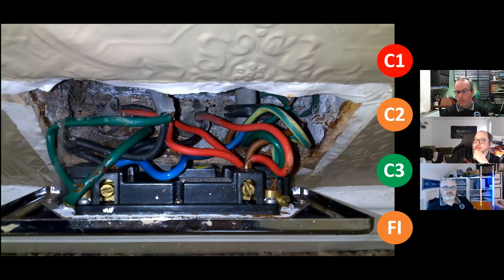Okay, so you've just gone through. You've come up with a C3FI, correct? Yeah. Just based on that visual alone. Mm-hmm. But so what would escalate you here to the C2? Knowing my luck, putting it back and it going bang. Maybe a sound of crackling, maybe evidence that the connection's not sound if there's excessive heating.